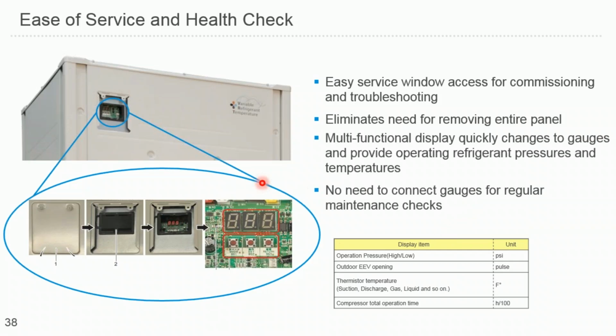Also, this 7-segment display will work as a multifunctional display. Basically, this is a summary of what you will be able to read through those indicators: the refrigerant temperatures, pressures, outdoor unit EEV openings, even the compressor's total operation time, without using your service checker or the gauges that you might want to use to measure temperatures and pressures and whatnot.